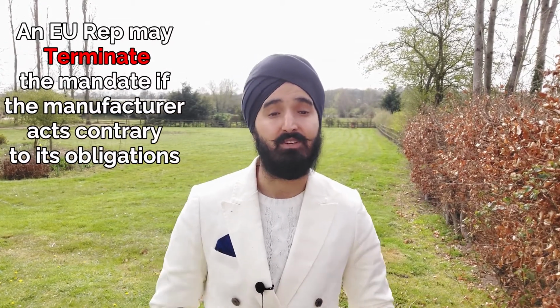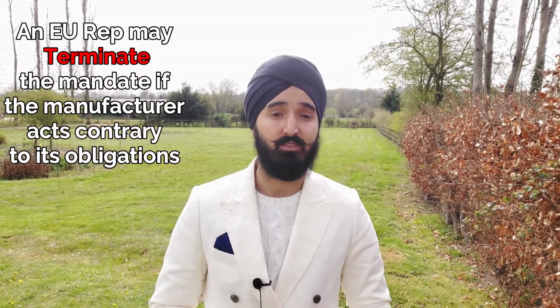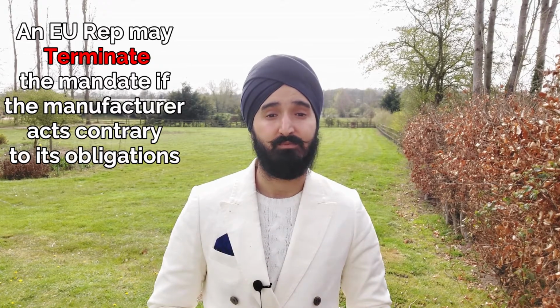They're also required to cooperate with competent authorities on any field safety corrective actions, recalls or ship holds, and immediately inform the manufacturer they represent of any known complaints or reports about their devices. If they deem a manufacturer not to be acting to the required regulations, they may terminate the agreement at any given time and let the relevant competent authorities know about this and the reasoning for doing so. Hence why it is important to choose wisely.